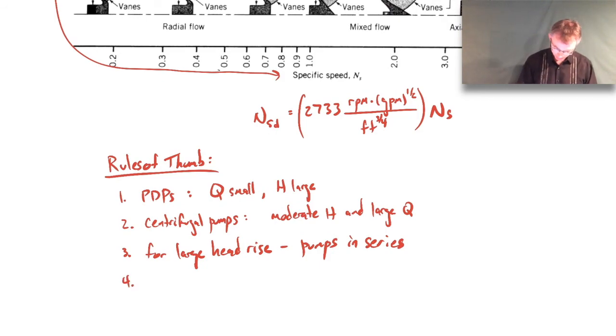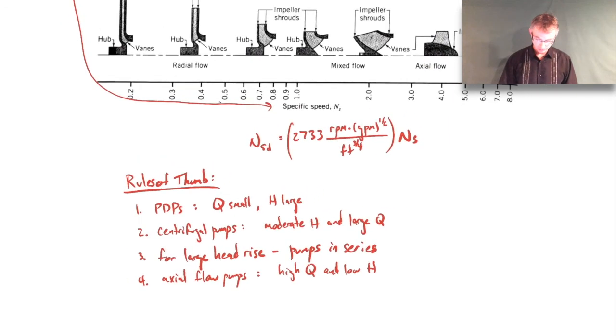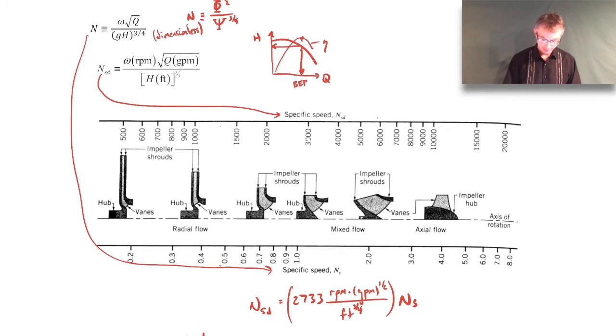And then the last rule of thumb is axial flow pumps. Those are for high flow rate and low head rises. And again, you can sort of figure those things out just from the specific speed since the specific speed again has the flow rate in the numerator and the head rise in the denominator. So large specific speeds means large flow rates, smaller head rises. Lower specific speeds correspond to lower flow rates, higher head rises.